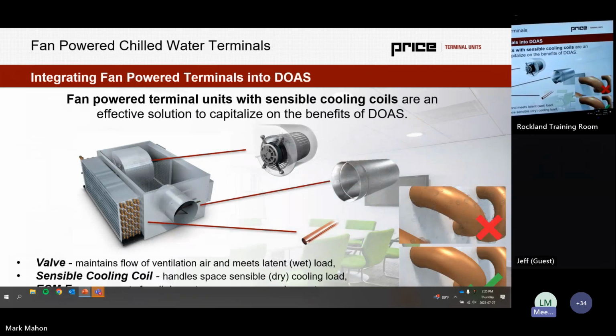So once again, this product is sensibly cooling air through its return. We have an offset in volume between the fan and the primary air damper. That offset is induced through the coil on design day for heating in the winter, or for cooling to offset design day in the summer. We're able to measure and control primary airflow with our fresh air inlet, which has a full cross-flow sensor and damper, which is going to allow for demand-controlled ventilation. And mandatory on these products is EC motors. EC motors, for the most part, are being viewed as mandatory anywhere we're using fractional horsepower motors because they're so much more efficient. However, their longer lifespan, their higher capabilities for static pressure, and their capabilities to sequence and change their volume set point throughout operation are all humongous assets. So lots of considerations there.